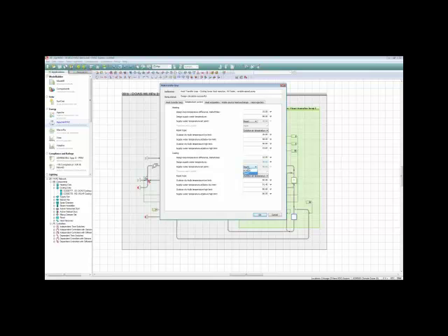And we can control that temperature set point. And because this is a heat transfer loop, because it has both heating and cooling functions, it basically has a sort of a dead band in which the temperature is allowed to float, and an upper limit on the cooling side and a lower limit on the heating side as a resource then for other devices to put heat on the loop or take heat off the loop.